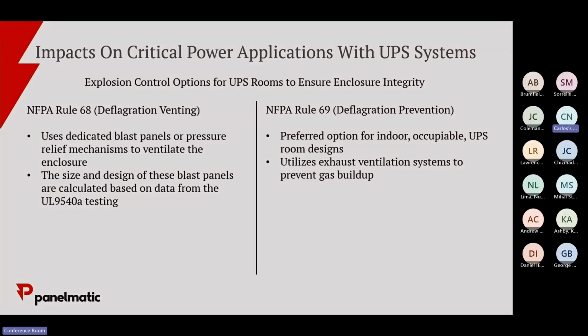So again, the two types of rules I was talking about before, Rule 68 and Rule 69. Rule 68 deals with deflagration ventilation. This is a traditional BESS design, so you're talking just batteries, large scale, heavily energy dense system, typically 1+ megawatt, 3 megawatt hours or more, and it's going to have deflagration panels.